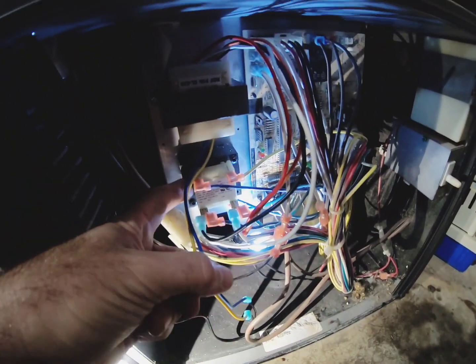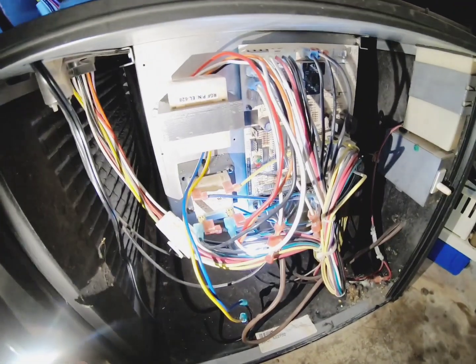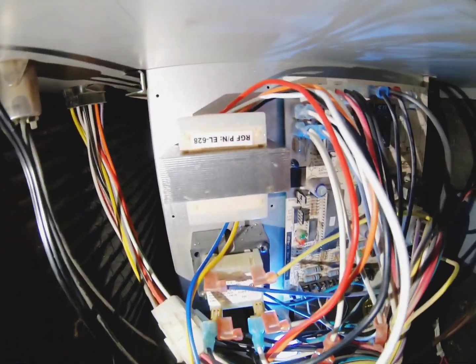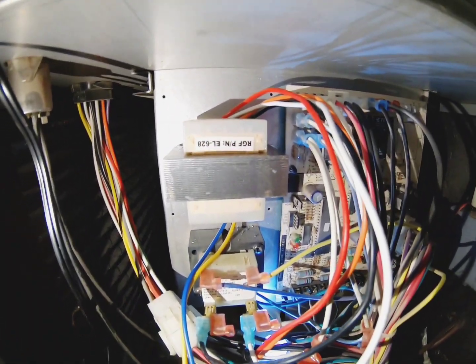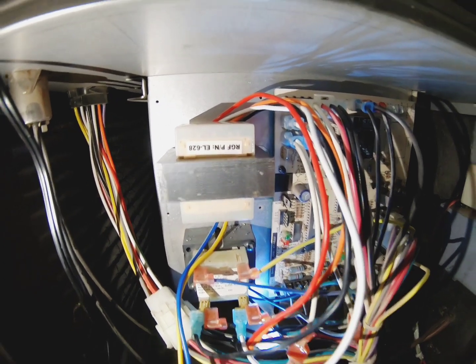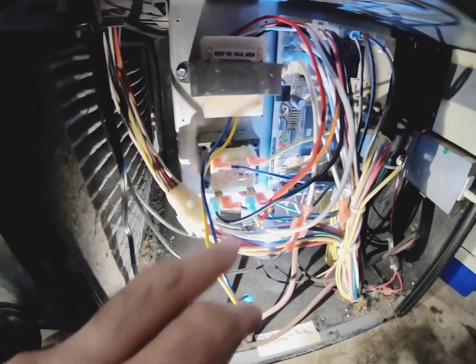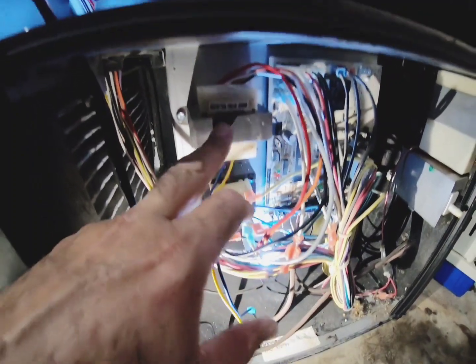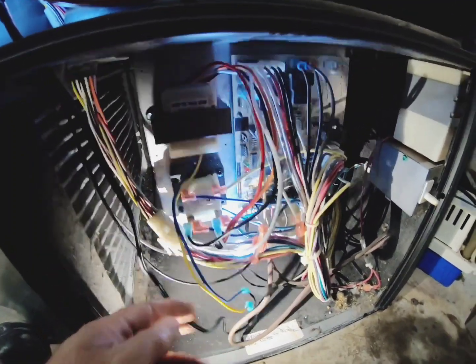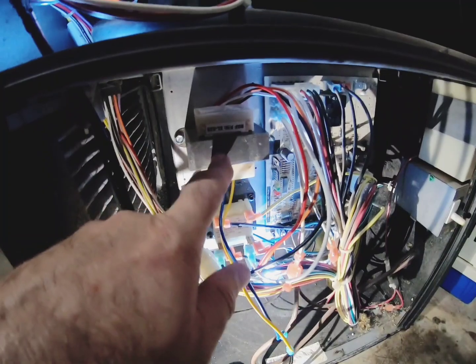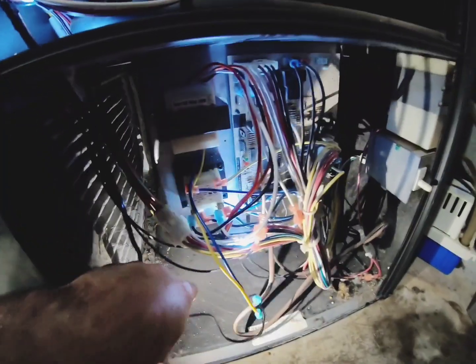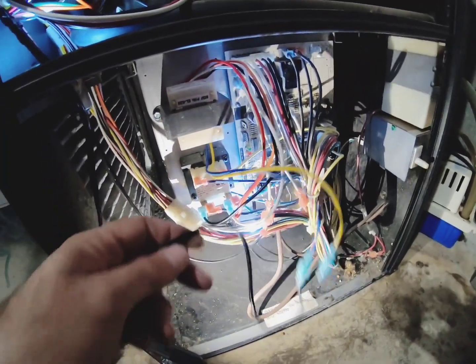So I didn't want to use the original transformer that came inside of this furnace. What I wanted to do was add another transformer in order to power the APCO-X and isolate it from the rest of the unit. So what I did was just piggyback the 120 over to the new transformer, and we picked up our 24 volts right here for the APCO-X. Now we just got to do a little bit of cable management, turn this thing on and test it.